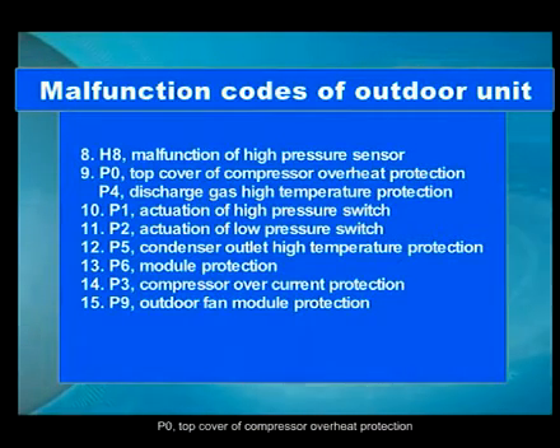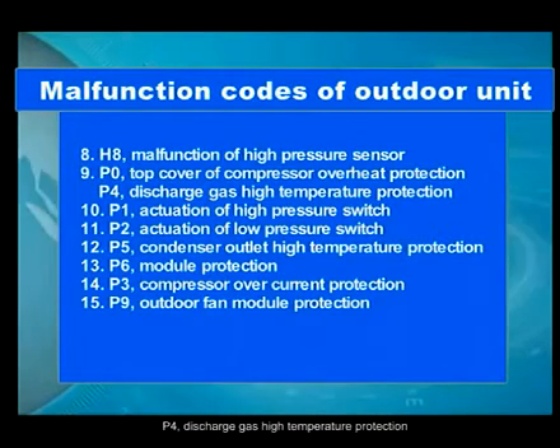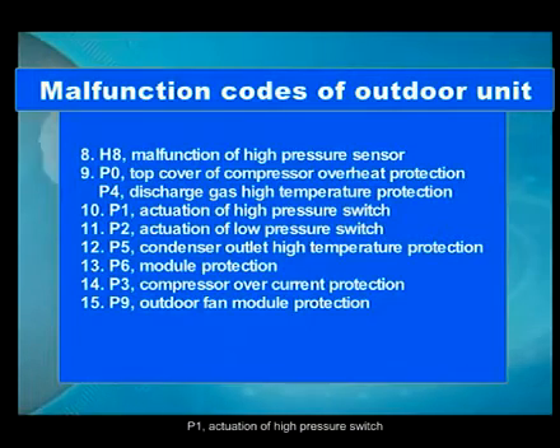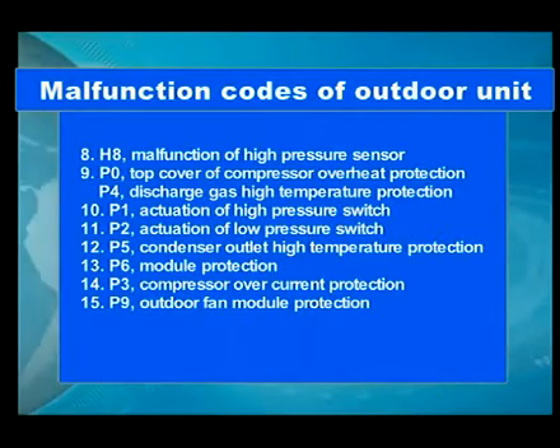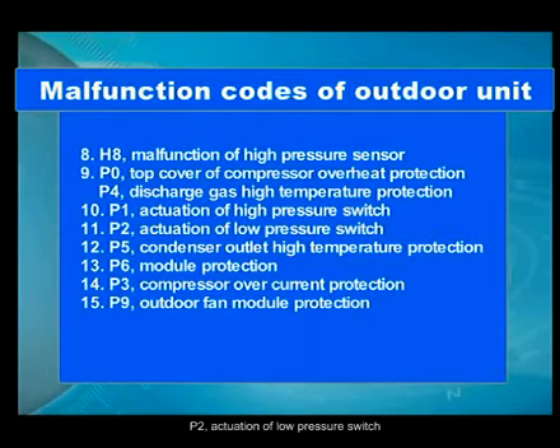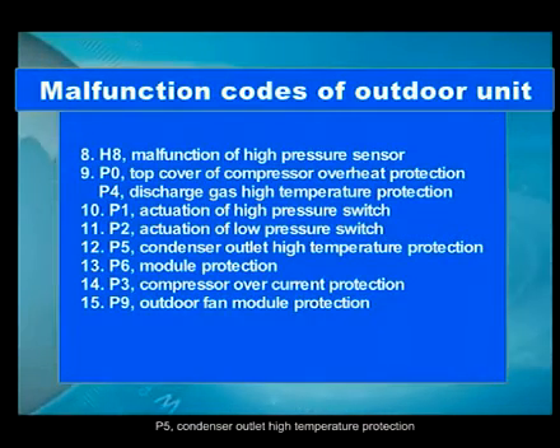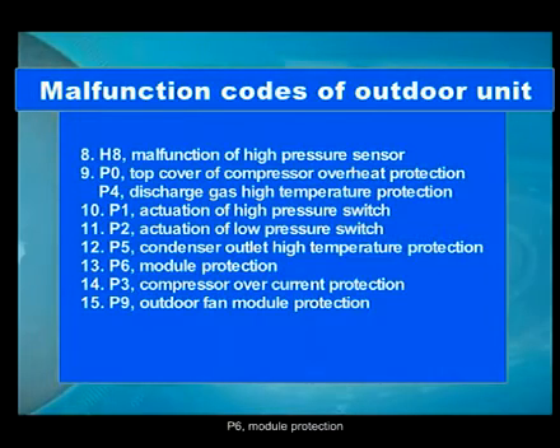P0. Top cover of compressor overheat protection. P4. Discharge gas high temperature protection. P1. Actuation of high pressure switch. P2. Actuation of low pressure switch. P5. Condenser outlet high temperature protection. P6. Module protection. P3. Compressor over current protection. P9. Outdoor fan module protection.